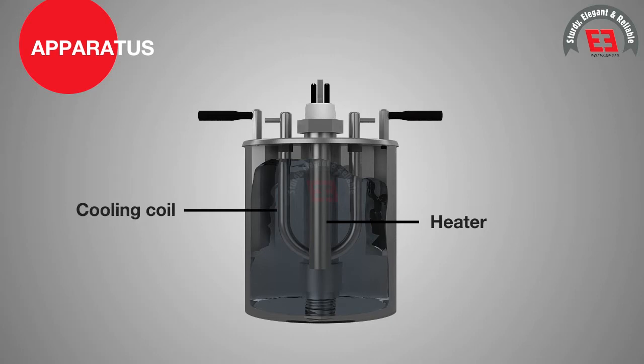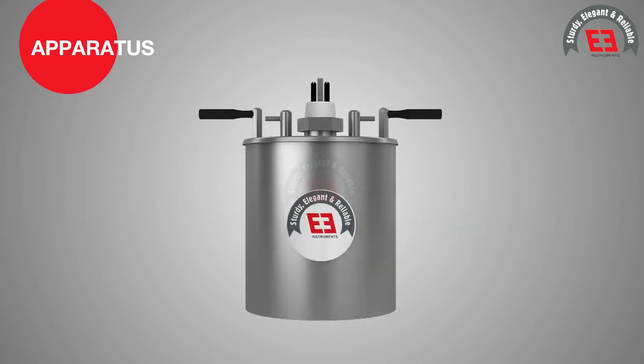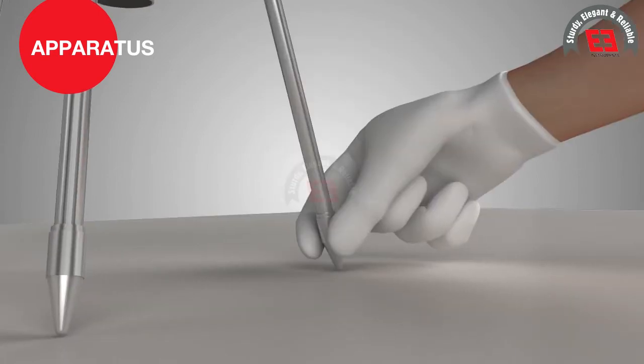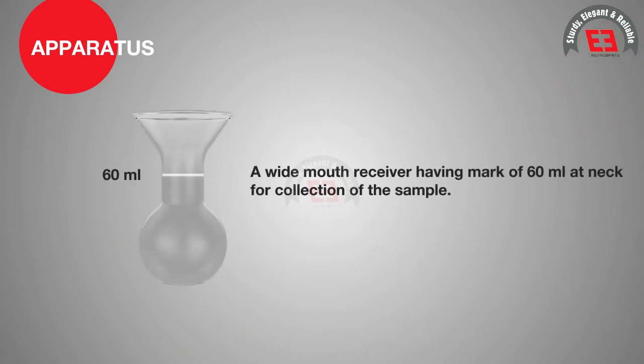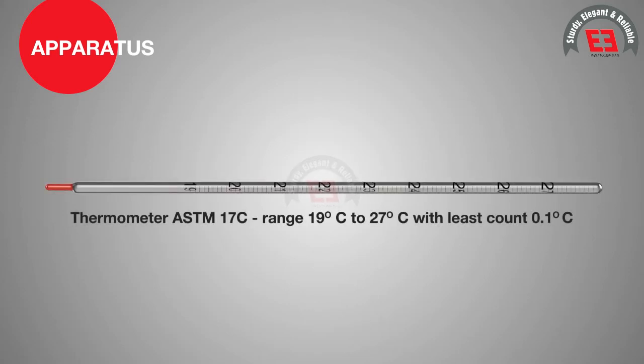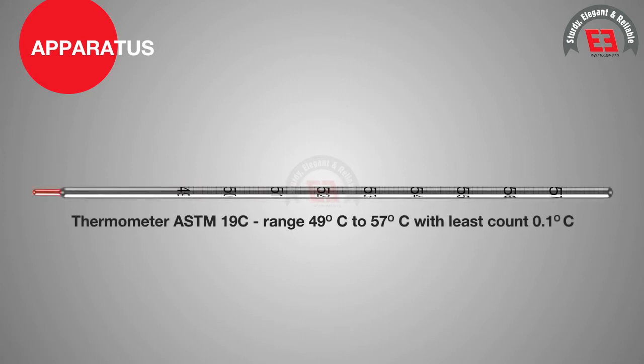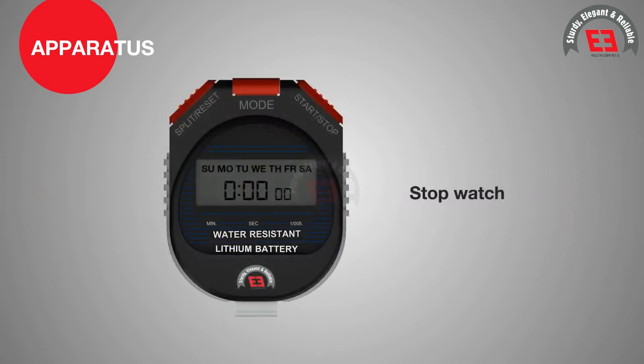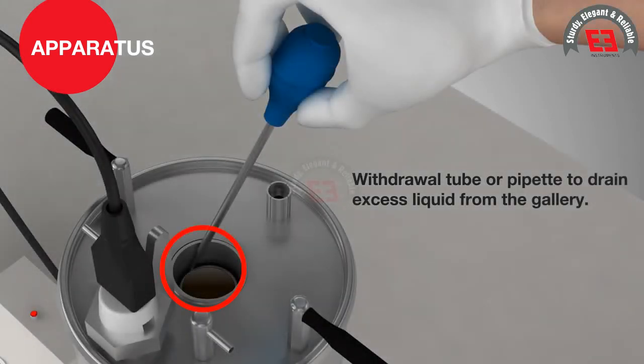The lid of the water bath has a heater and cooling coil to bring the temperature of the bath media up or down. The bath is placed on a tripod stand with leveling arrangements. A wide mouth receiver with a mark of 60 ml at the neck is used for collection of the sample. A thermometer ASTM 17C, range 19 to 27 degrees Celsius, with a least count of 0.1 degrees Celsius, a stopwatch accurate to 0.1 second, and a withdrawal tube or pipette to drain excess liquid from the gallery are also required.